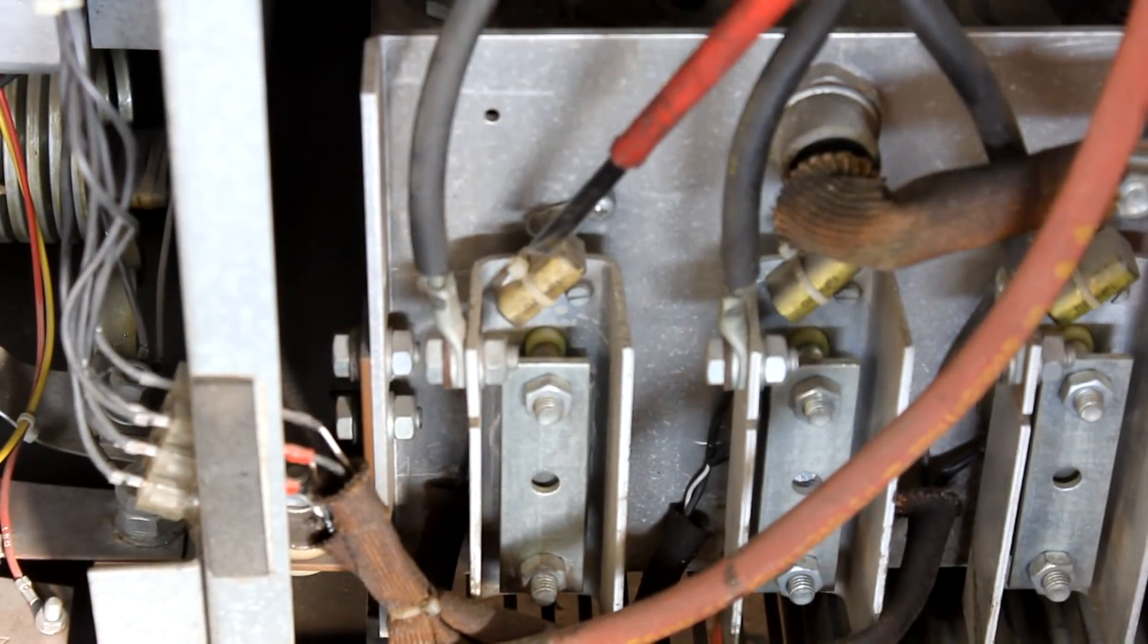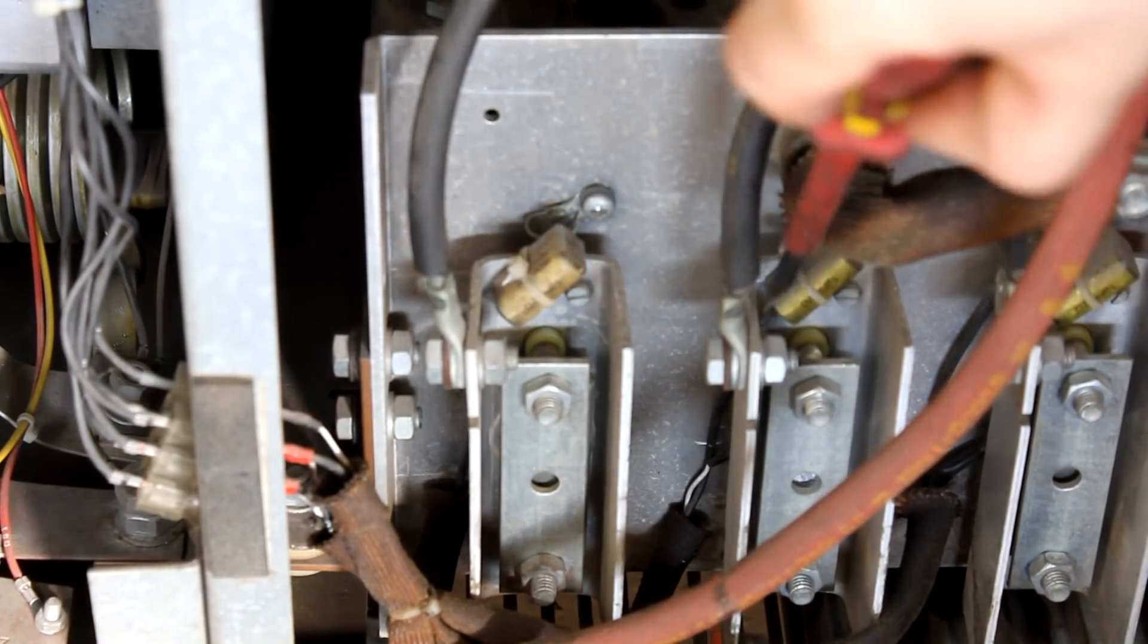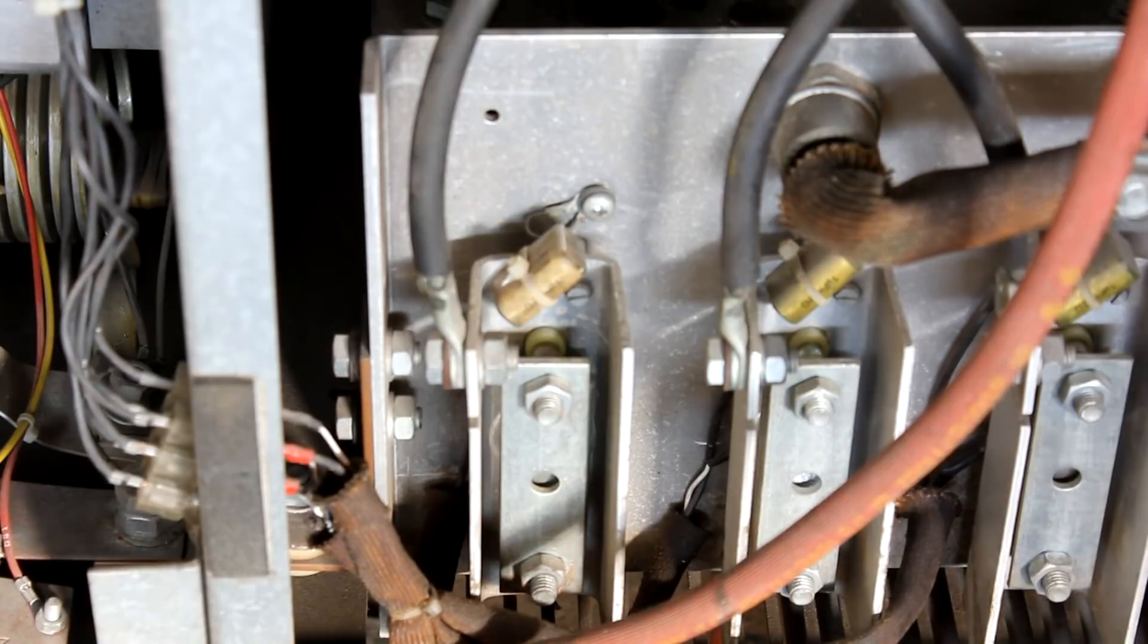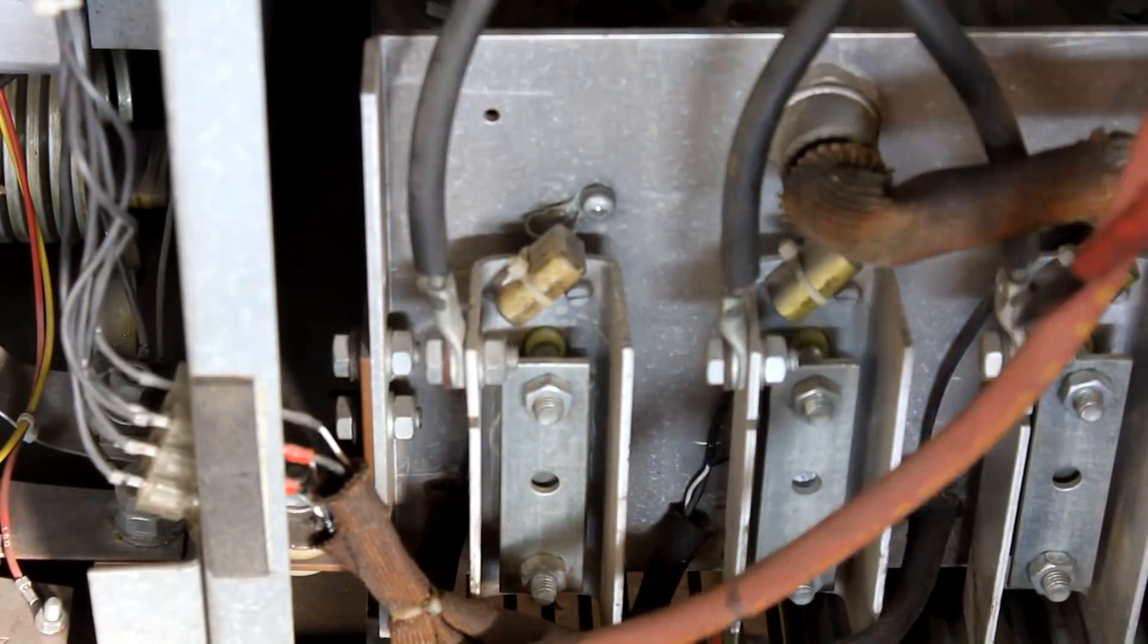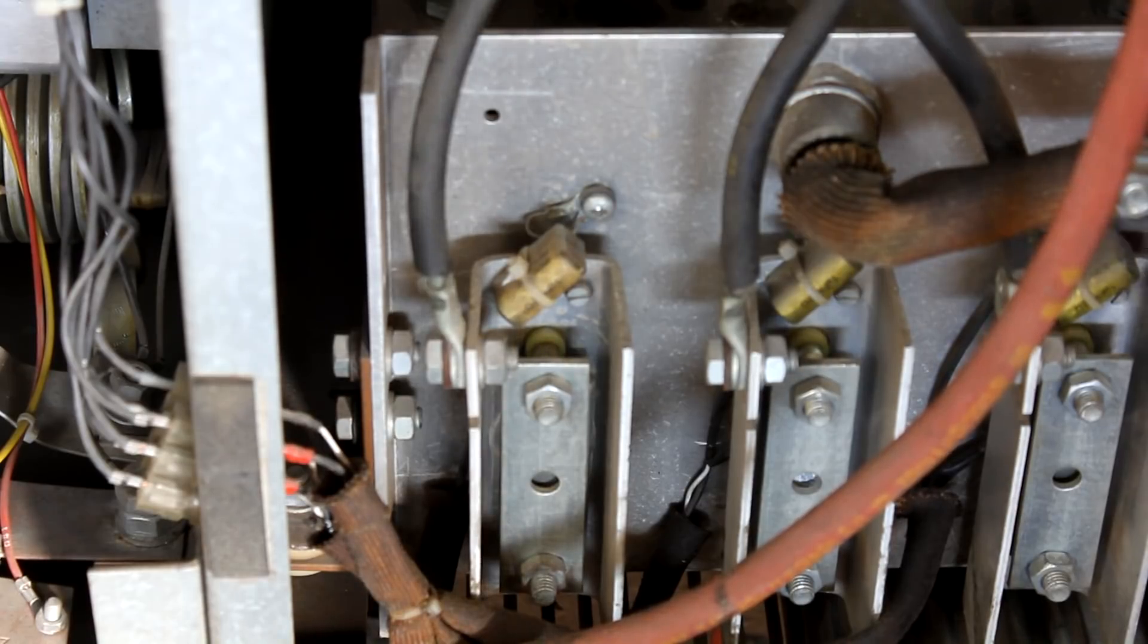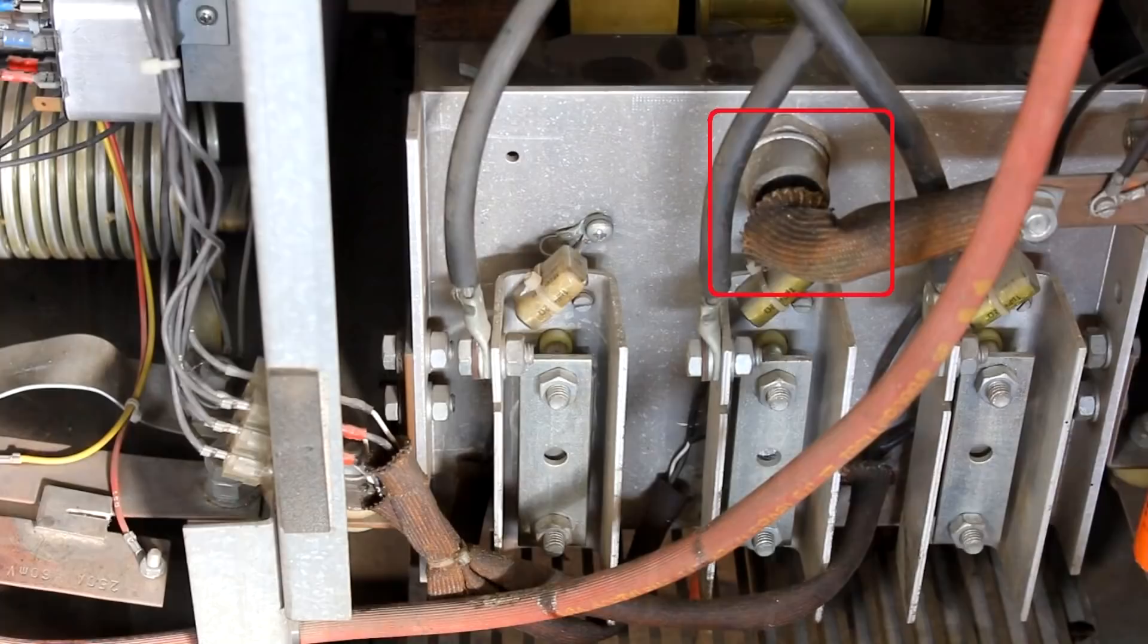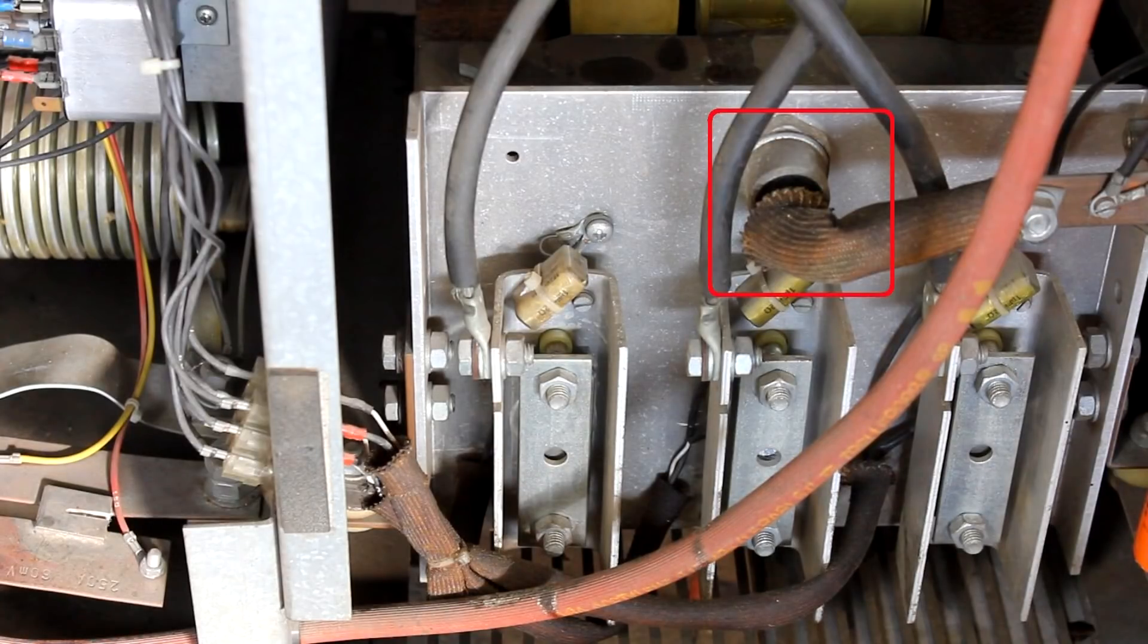That comprise the other half of our three-phase rectifier here. And I'll show you that in a schematic in just a minute. Now, on top of these SCRs, we also can find, again, little suppression caps, or in this case, probably rather integrated RC circuits or snubbers that contain the same kind of cap, though. And probably one or more is also damaged. We also find this large high-current diode here. And I'll explain what that's good for later on as well.